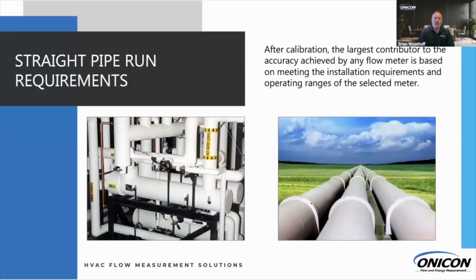So we like to talk about the straight run, mainly so that we can achieve those accuracies, especially in those applications where we're billing on thousands of dollars on these flow meters. So we have to achieve the best straight run. In an ideal world for a manufacturer, we dream of this on the right, but obviously we know we're typically dealt a mechanical room that looks like that on the left. So if you are having difficulties finding that straight run, definitely reach out to ONICON and we can help assist, looking at maybe the supply versus the return and so forth on a closed loop system.